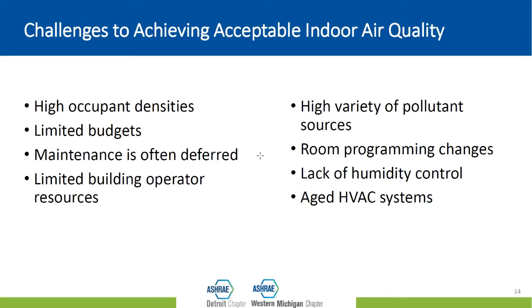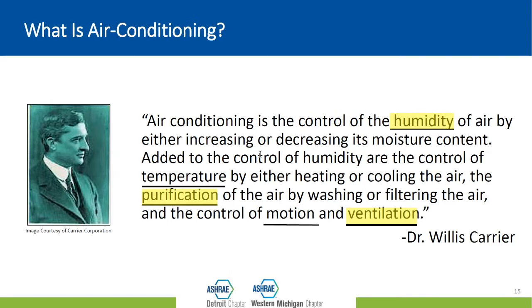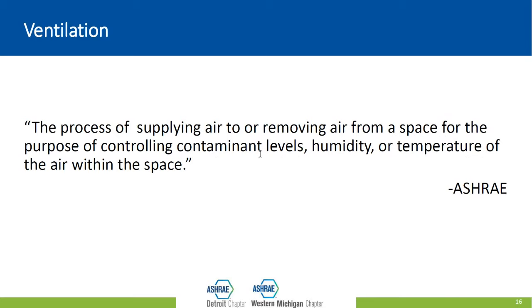So now what is it that we're asking this equipment to do? Next slide. When the average person thinks of air conditioning, they often think of just cooling the air, right? But air conditioning is actually much more than that. It includes control for temperature, plus control for humidity, air cleanliness, air motion within the occupied space, and introduction of new air into that space. Today, we're going to talk about 3 of these air quality characteristics: filtration for cleanliness, humidity, and ventilation. We'll start with ventilation. Next slide. This is the process of supplying air into or removing air from a space for the sole purpose of controlling contaminant levels, humidity, and temperature of that air within that space.